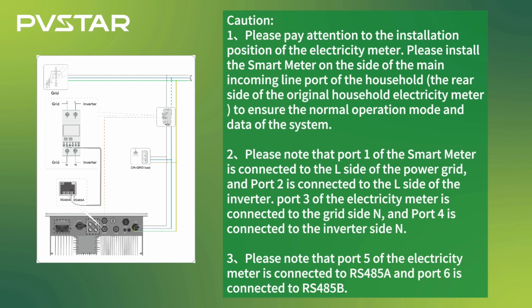Secondly, please note that port 1 of the smart meter is connected to the L side of the power grid, and port 2 is connected to the L side of the inverter. Port 3 of the electricity meter is connected to the grid side N, and port 4 is connected to the inverter side N. Thirdly, please note that port 5 of the electricity meter is connected to RS485A, and port 6 is connected to RS485B.